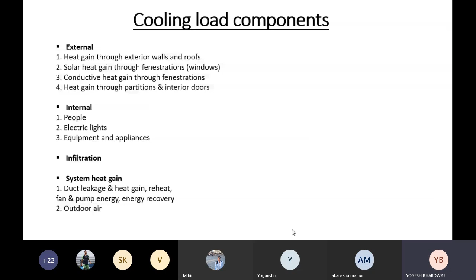So okay, before going into how we calculate the heat load from walls or from roofs, we first need to understand the U value. So what is the U value? U value is termed the overall heat transfer coefficient. It is the rate of heat flow through a unit area of building envelope, material or assembly, including its boundary films, per unit temperature difference between the inside and outside air. So basically, you can call it the overall effect of conductance and convection. The lower the U factor, the greater is the material's resistance to this heat transmission.